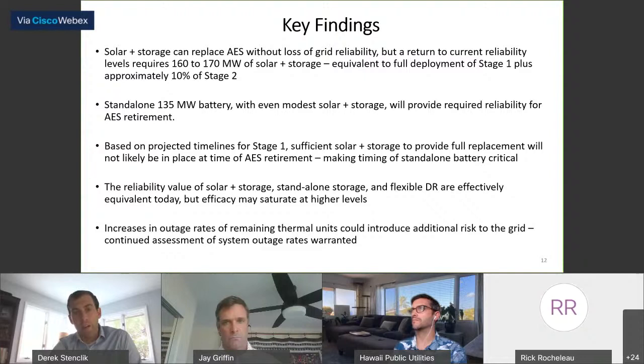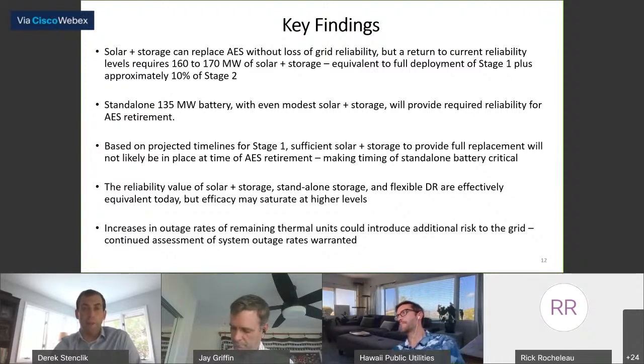But it's important to note those resources are effective at providing reliability. Second key finding: the standalone 135 megawatt battery, even with modest solar plus storage deployment, could provide the required reliability for the AES retirement. So even with the timing risk, as long as that 135 megawatt battery is in place, you can get back to current levels of reliability. Based on projected timelines for stage one, sufficient solar plus storage for full replacement will not likely be in place at the time of the AES retirement, making the timing of that standalone storage critical.